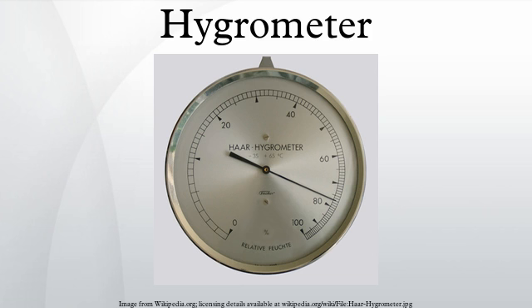Gravimetric hygrometer. A gravimetric hygrometer measures the mass of an air sample compared to an equal volume of dry air. This is considered the most accurate primary method to determine the moisture content of the air. National standards based on this type of measurement have been developed in the US, UK, EU and Japan. The inconvenience of using this device means it is usually only used to calibrate less accurate instruments, called transfer standards.